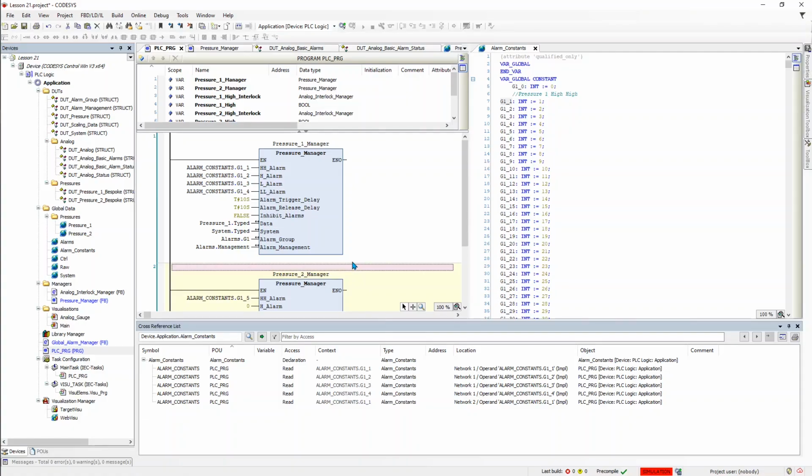So now that outlines the basic approach to this, so we have a manager which is expecting numerical inputs, so it knows where it's supposed to be indexing, and then everything else is passed as structures. We saw in a previous lesson that if we're passing in-out, it's much more efficient than passing all of these alarms just as a standard interface. So because they're in-out, they're by reference, and that really speeds up the execution time, as opposed to passing them in or creating copies of them via an input interface.